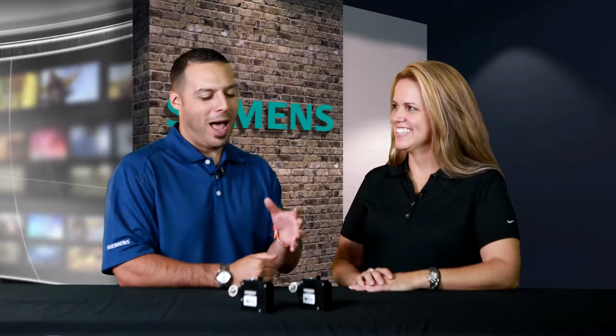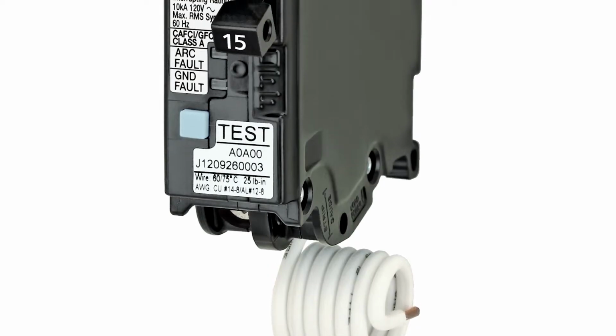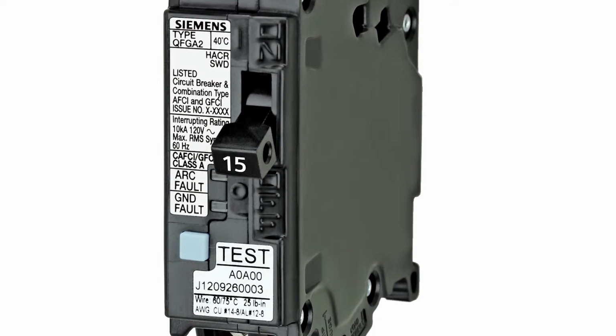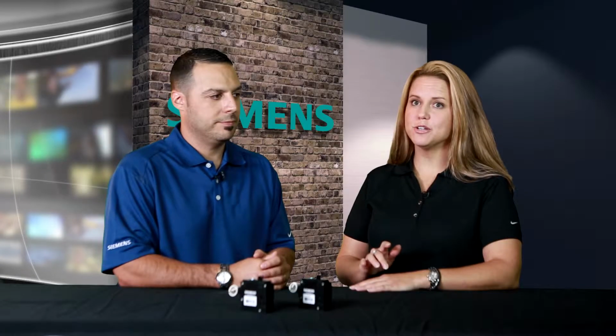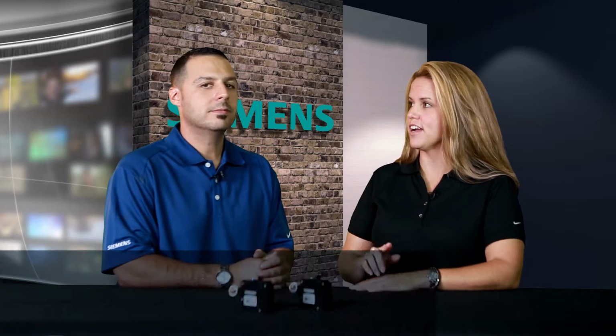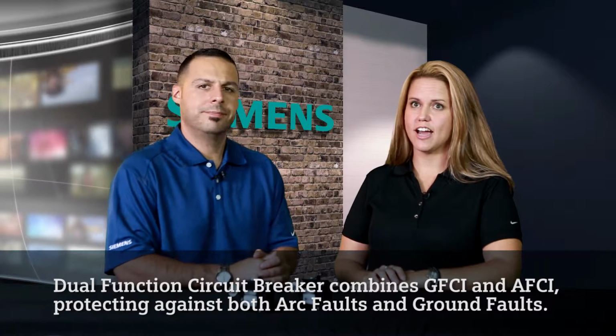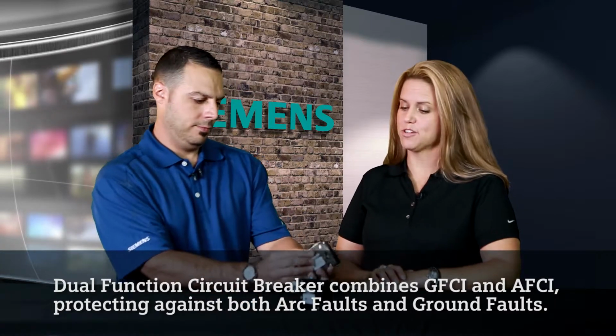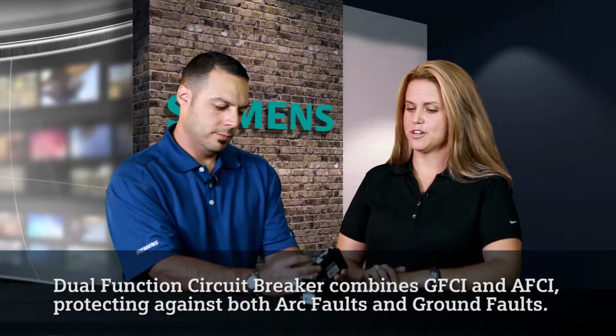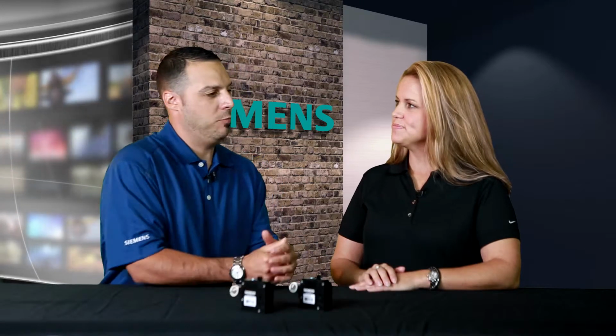Doing great. Now, how does this particular breaker differ from either the arc fault or even the combination arc fault circuit breaker? Yeah, so the combination arc fault circuit breaker actually provides series and parallel arc fault protection. The dual function now combines two technologies into one device. Okay. So now we have the AFCI, the arc fault protection, as well as the ground fault protection in one circuit breaker. Okay. Pretty good information.